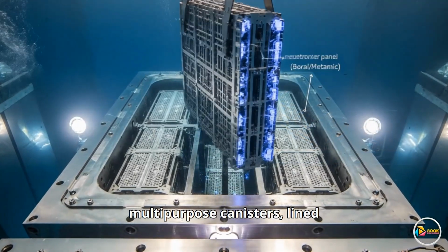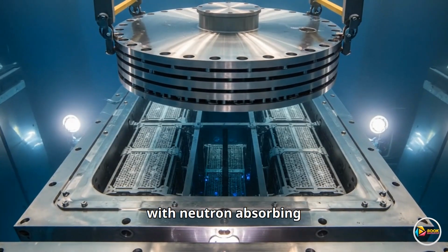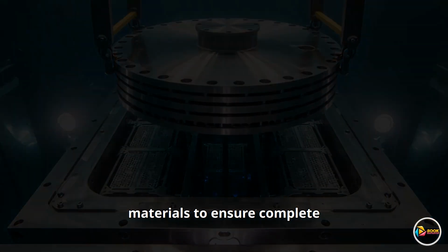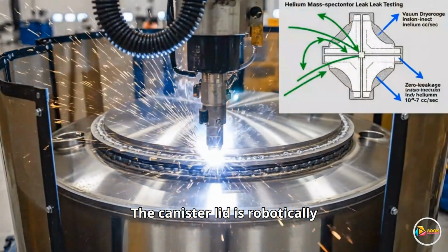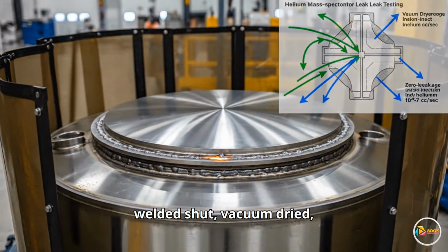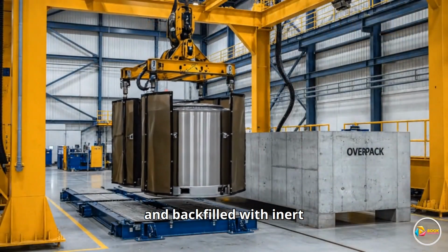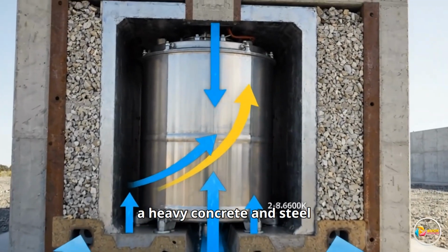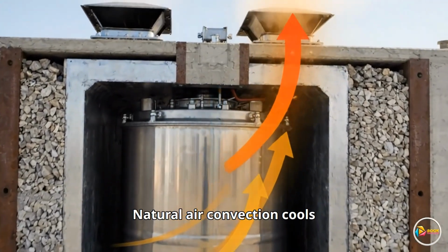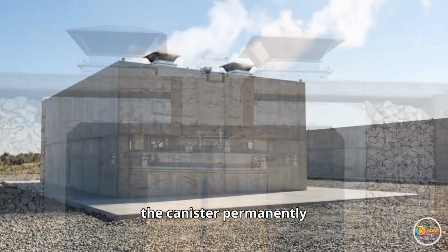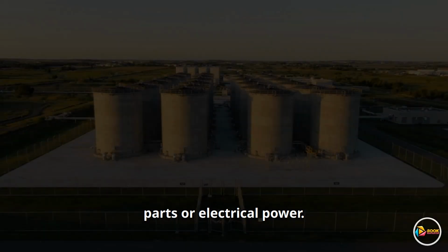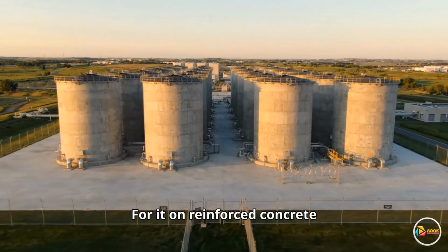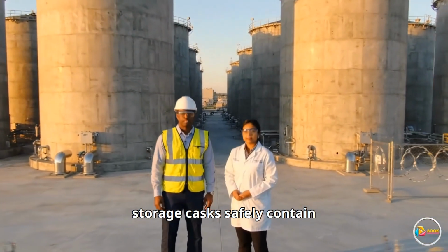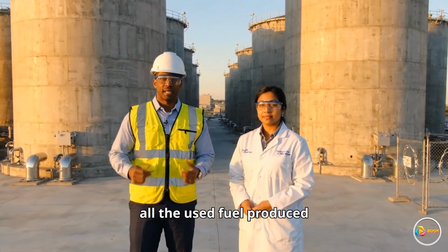Spent fuel is loaded underwater into thick stainless steel multi-purpose canisters, lined with neutron-absorbing materials to ensure complete safety. The canister lid is robotically welded shut, vacuum dried, and backfilled with inert helium gas. The canister is placed inside a heavy concrete and steel overpack. Natural air convection cools the canister permanently without needing any moving parts or electrical power. Stored on reinforced concrete pads, these passive dry storage casks safely contain all the used fuel produced over a plant's entire operating lifetime.